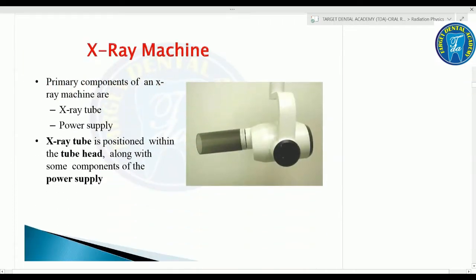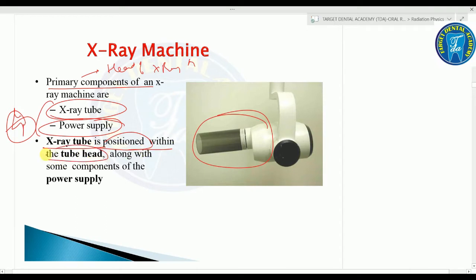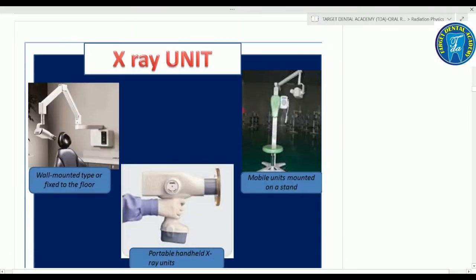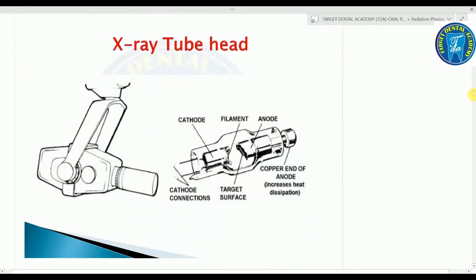The primary components — the heart of the X-ray machine — are the X-ray tube and the power supply. The X-ray tube is positioned within the tube head along with components of the power supply. There are three types of X-ray units: wall-mounted or fixed-to-floor type, portable handheld X-ray unit, and mobile unit mounted on a stand.